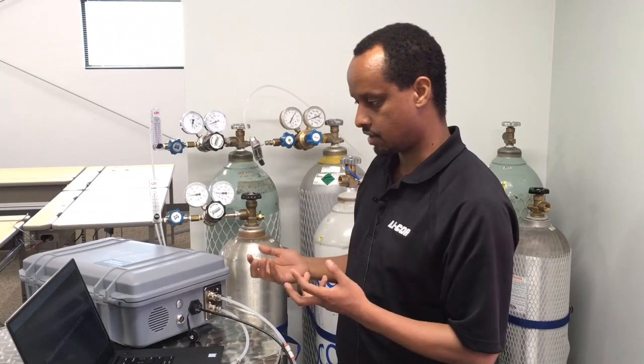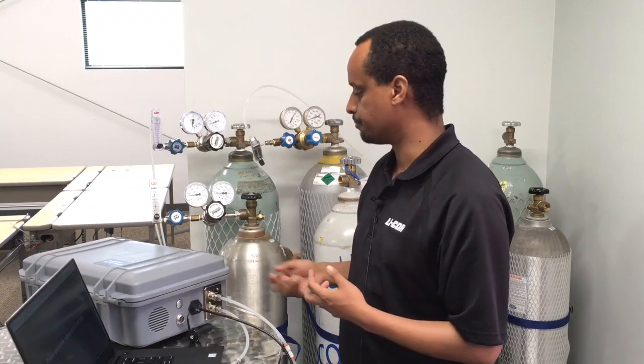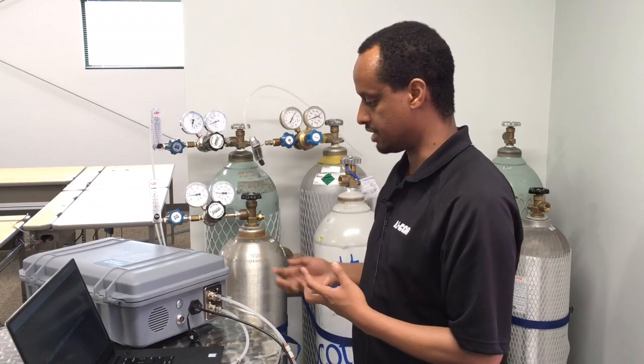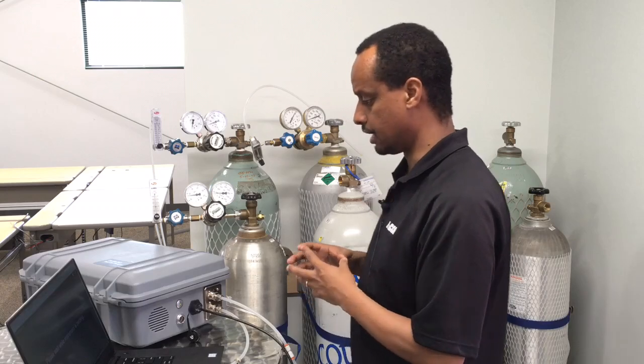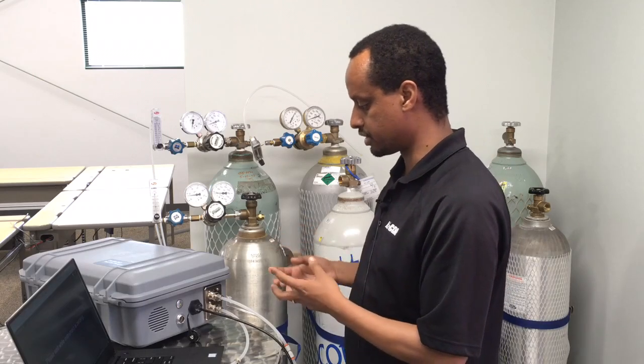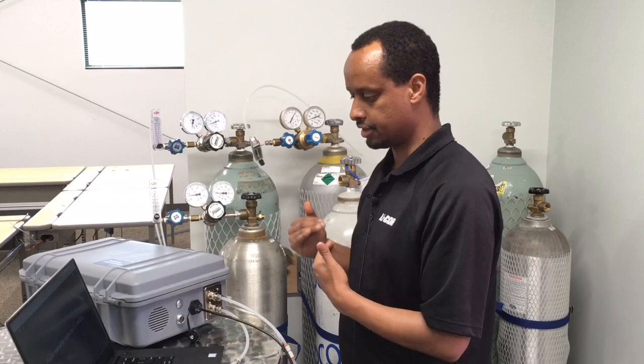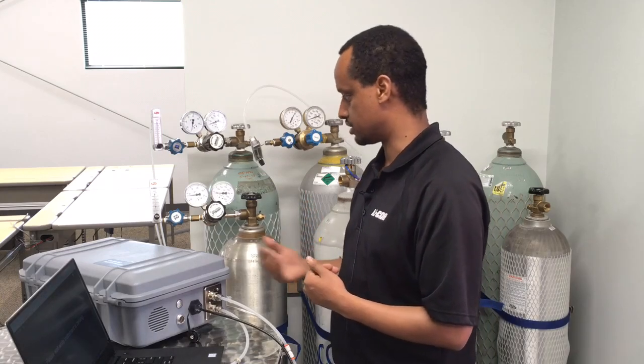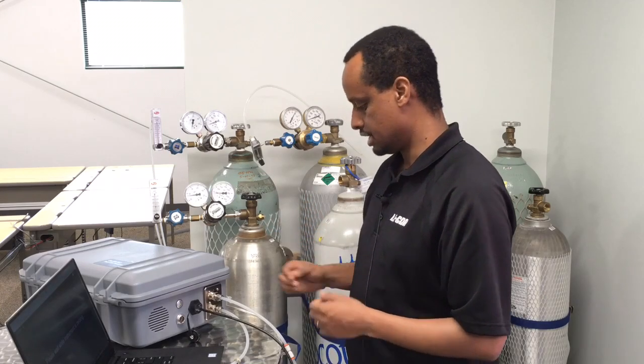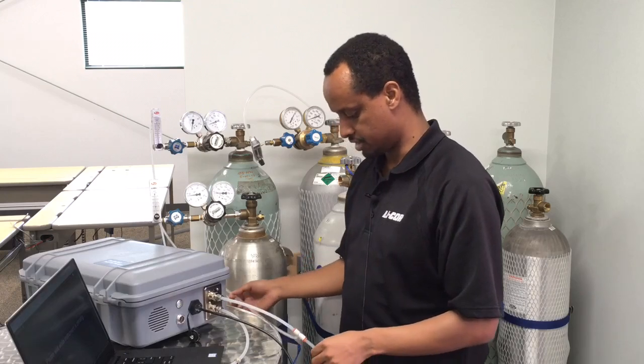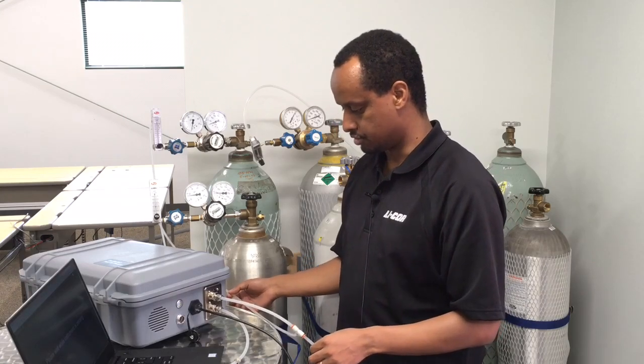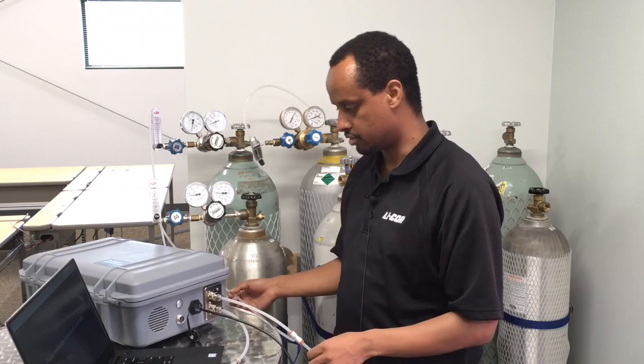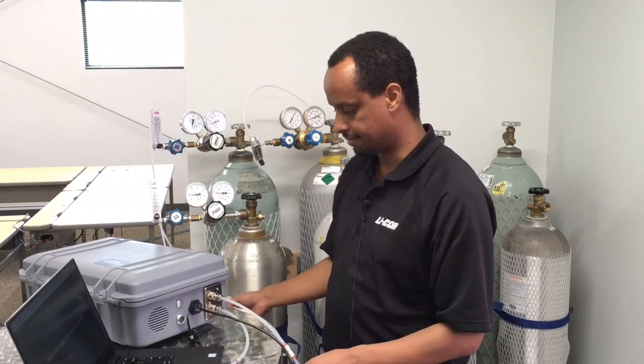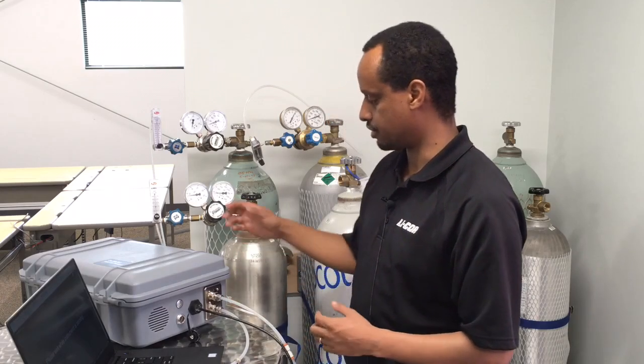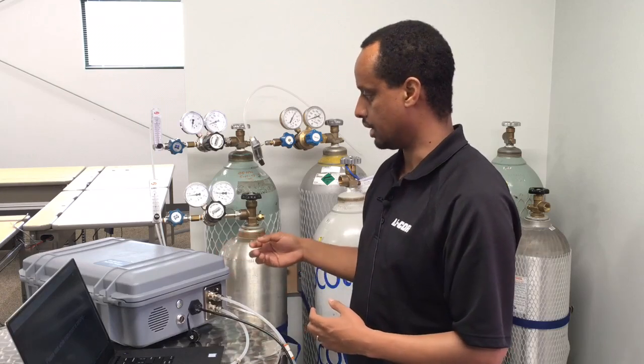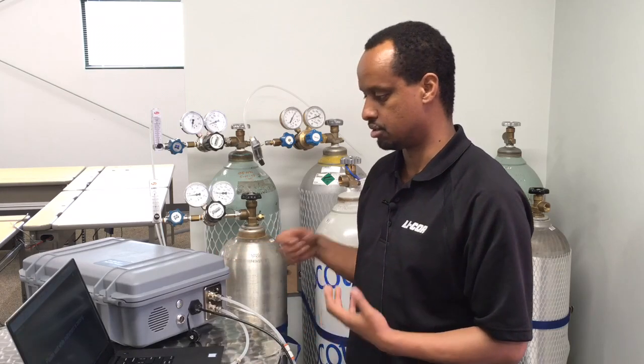So if that's a significant offset you want to correct for, you can do the zero. For span, we think the span is stable, and we don't expect more frequent calibrations, but if you have a very precise threshold for span, you can check that regularly and adjust as necessary. Now one more thing I will mention: I'm using plastic tubing to demonstrate this. If you're worried about small offset and small change in concentration, you want to avoid using plastic tubing and use metal tubing with compression fittings all around.